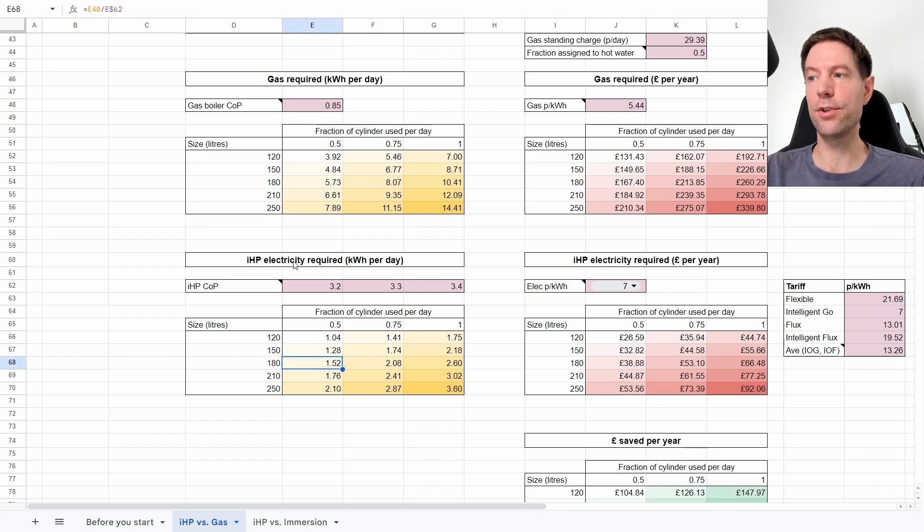And what we're interested in is this section here where I've labeled it IHP electricity required in kilowatt hours per day. So for Kat and I we're in this situation here where we have a 180 litre cylinder and we use about half of it per day, which means in order to reheat the cylinder from one day to the next we need a total of 1.52 kilowatt hours of electricity, which gives us a total annual running cost of about £38.88. So what I'm gonna do, I'm just gonna take a copy of that cell there, I'm just gonna stick it over here for no particular reason.